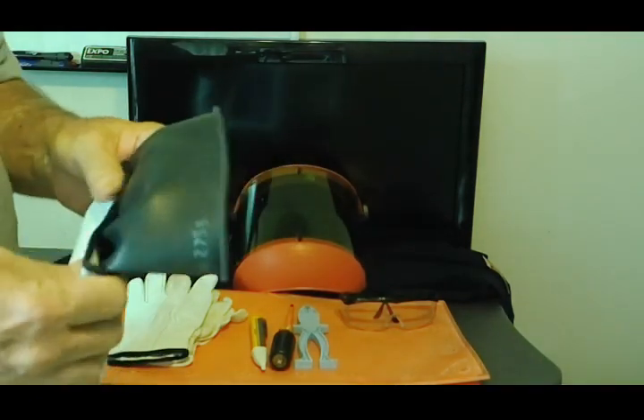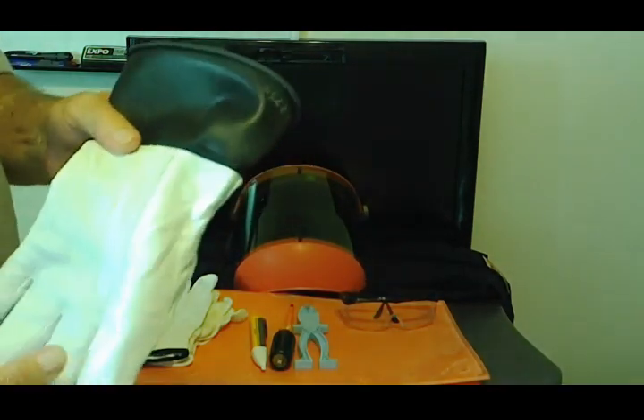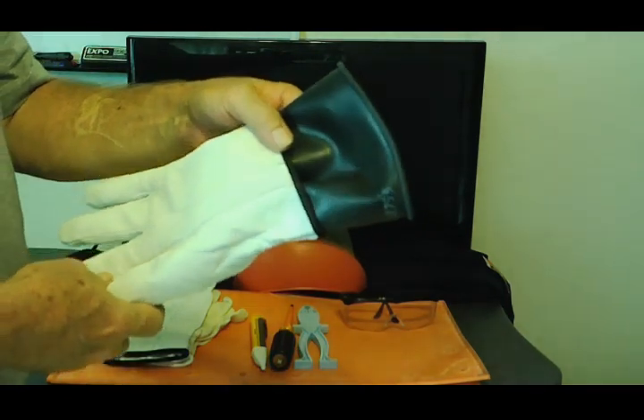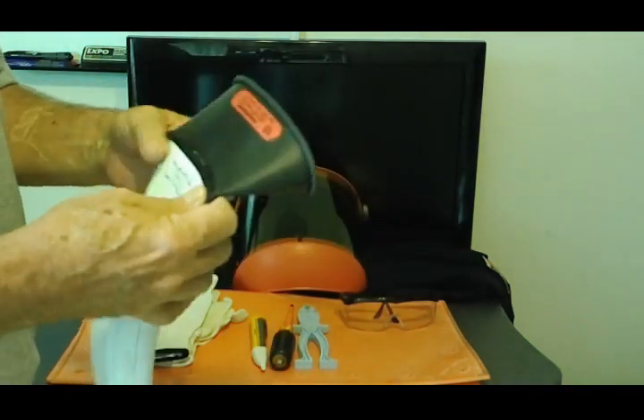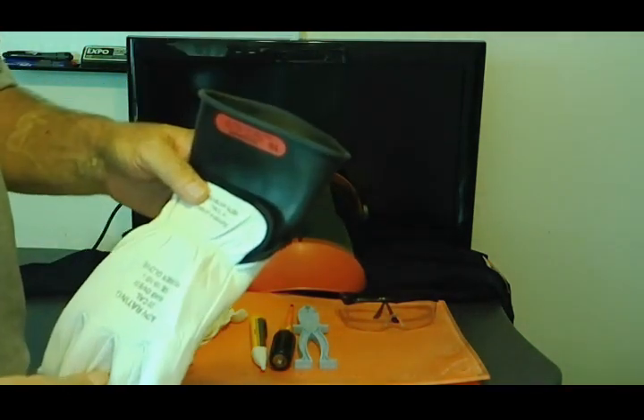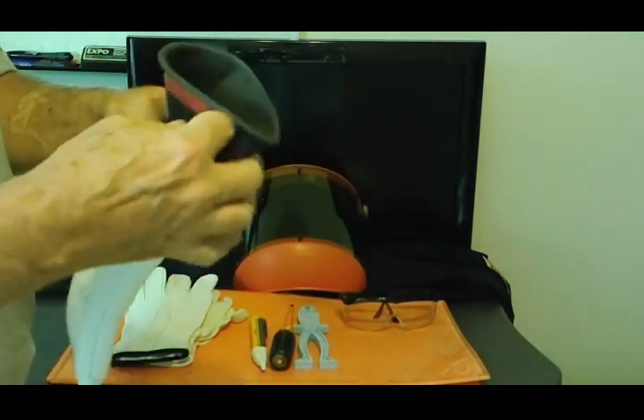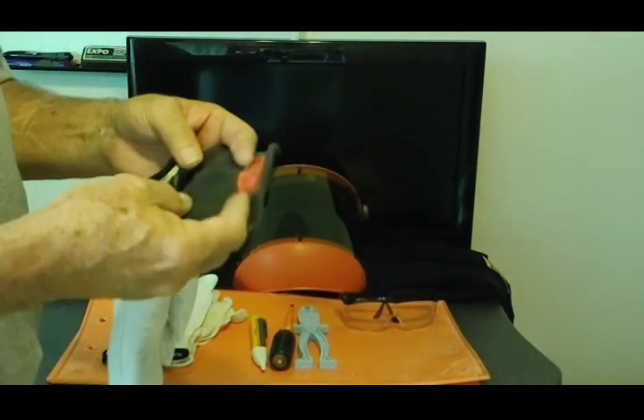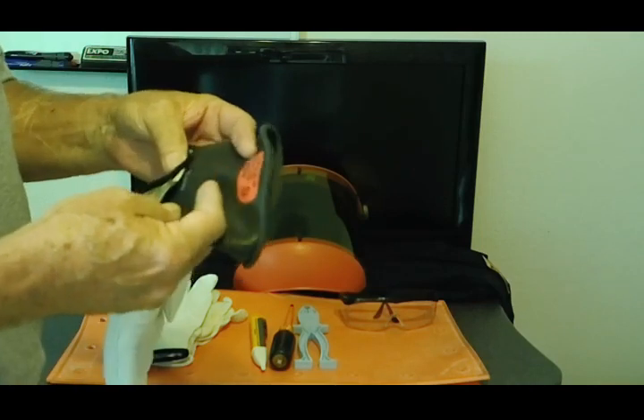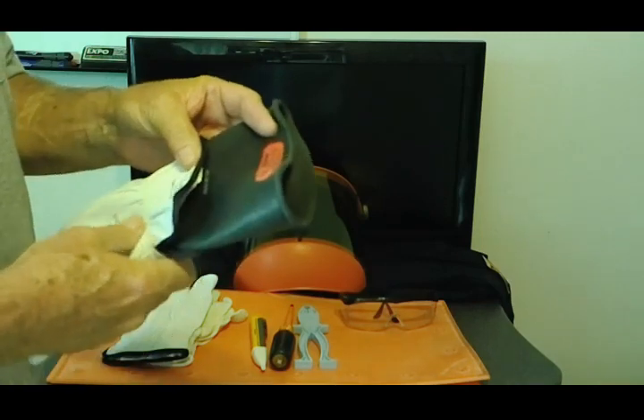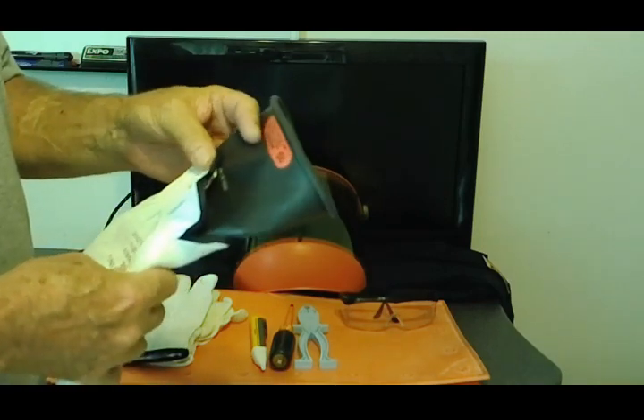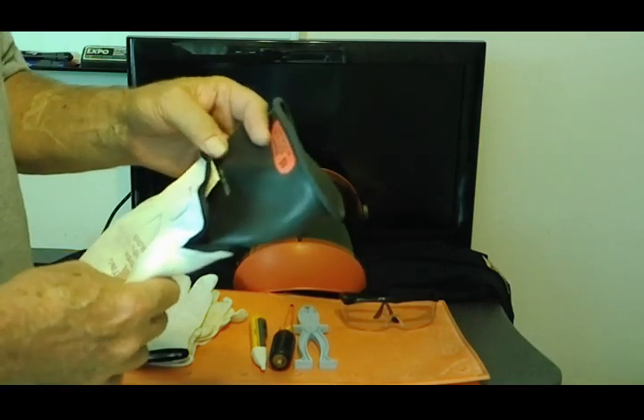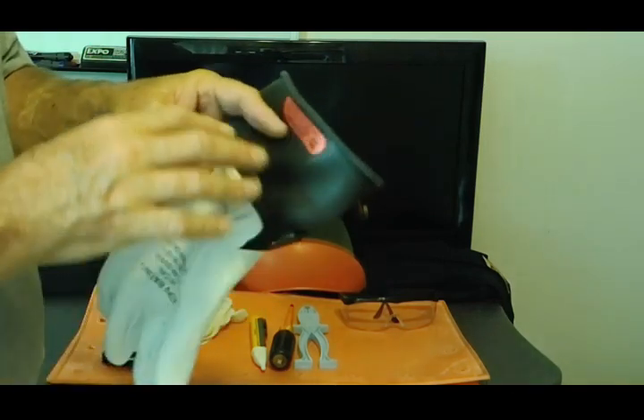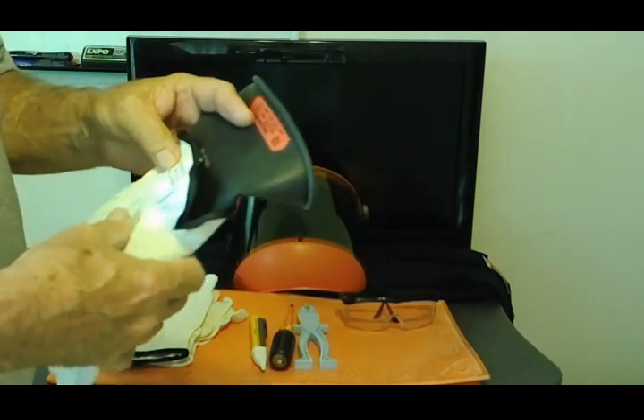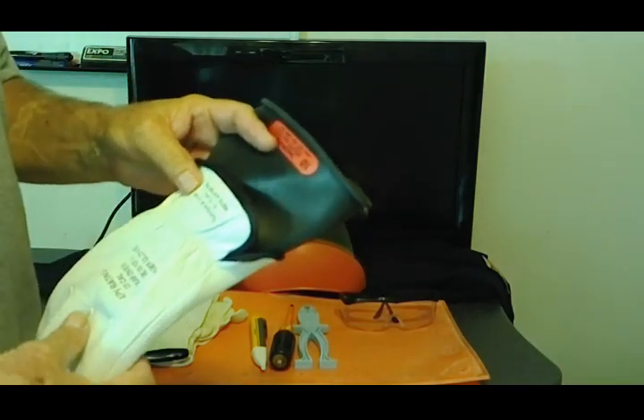So rubber gloves, now cleaning these gloves, never use any kind of petroleum-based powders or cleaners. About the only thing you want to use on these is water. If you get any kind of petroleum-based, or let's say soap, dishwashing liquids, whatever you're using on the rubber, this rubber is going to dry out, it's going to get sticky, it's going to crack, it'll just destroy it. The only thing these are used for to clean these is water. They do make specialized cleaners.